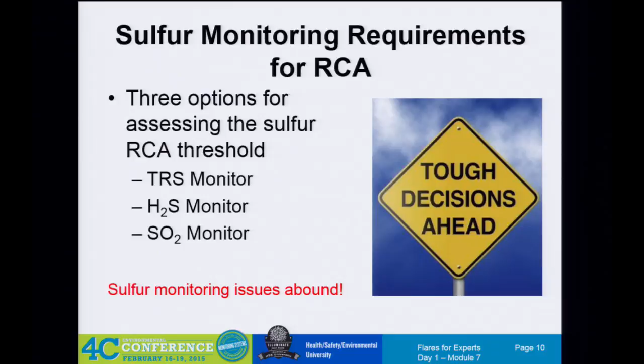Okay, for the RCA method and TRS monitoring, here they put in the span value. They didn't give you the nice round number of 300 so everyone knows what number it is. They decided it's got to be 1.1 to 1.3 times your maximum anticipated value. So basically, with this span requirement, they took away your ability to have a meter that's pegged out—you must always be able to measure what's in your gas. You can't say the monitor was pegged out, we guess it's about here. That's no longer allowed. But then they did set a lower boundary. So even if you say we're never going to get higher than 0.5%, you still have to span that upper range at 5,000 ppm, which, when you think about your cylinder gases, is still very toxic.